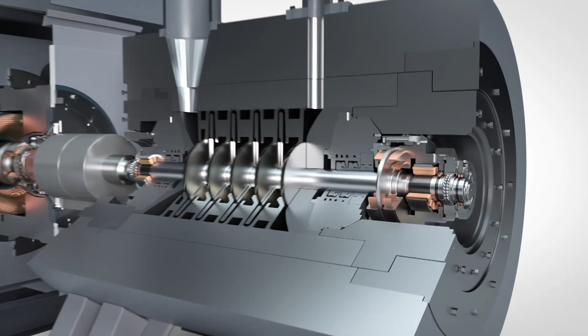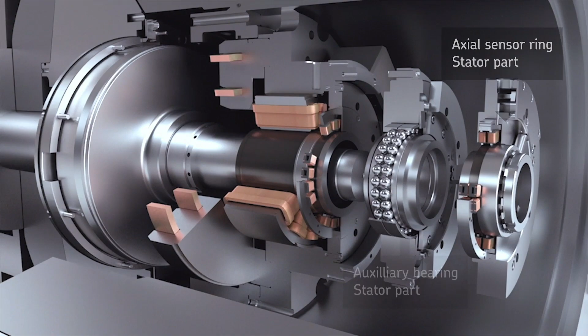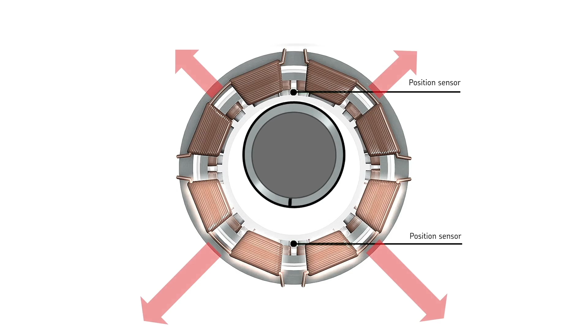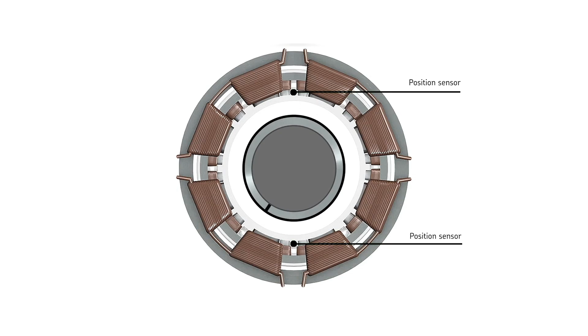Here is how it works. There is no contact between the rotating and stationary parts of a magnetic bearing. This means zero friction, no mechanical wear, no need for an oil lube system, and it's virtually maintenance-free. As the shaft rotates, proprietary position sensing technology tracks its precise position. A high-speed signal processing system continually adjusts the current flowing to the coil actuators on the stator. This keeps the shaft floating or levitating within the bearing.